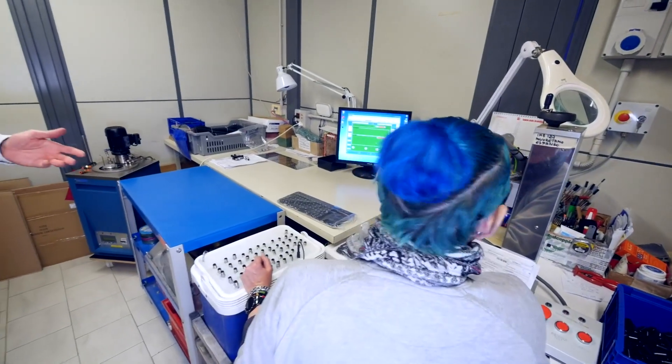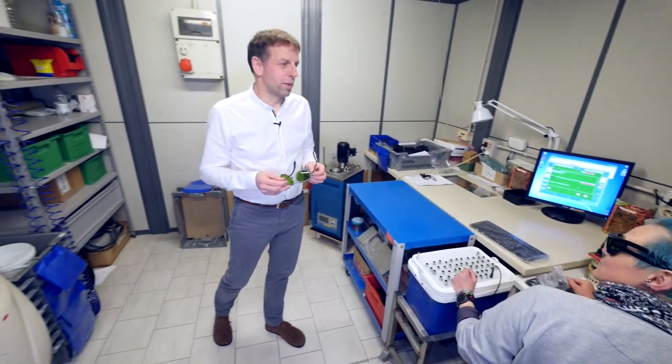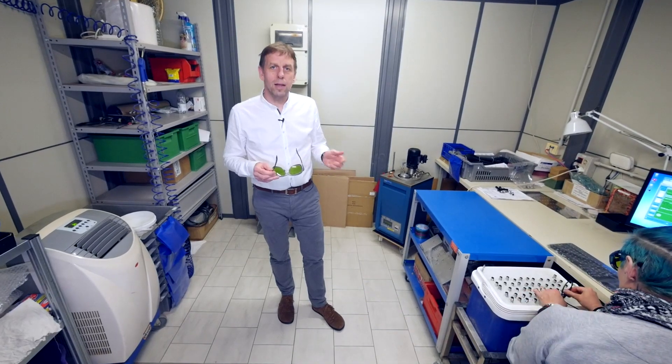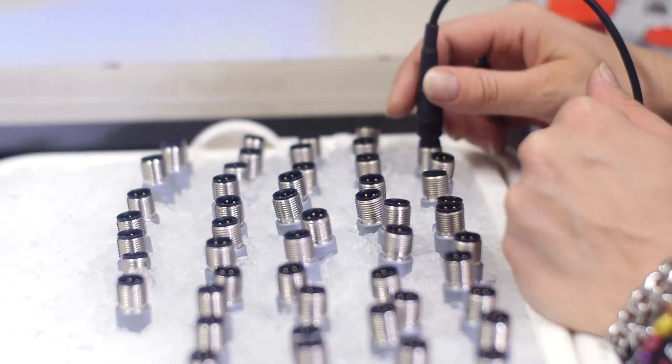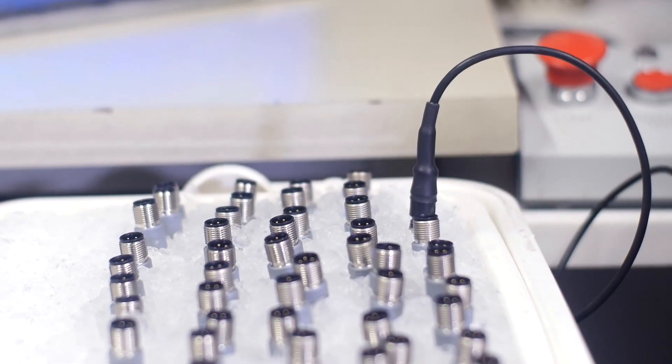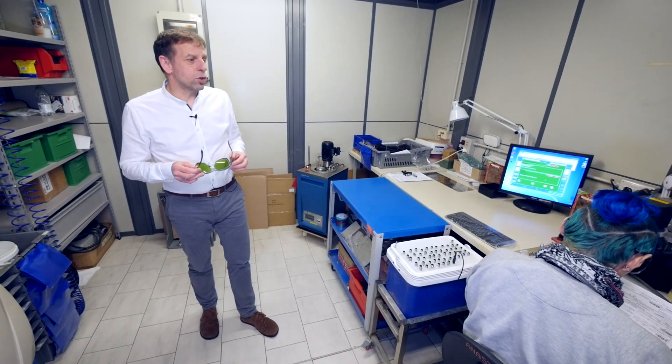Finally, a 100% test is performed. Each probe manufactured is electrically tested and measured in melting ice to find out the real resistance at zero degree. The value, as well as tracking information, is lasered onto the connector.